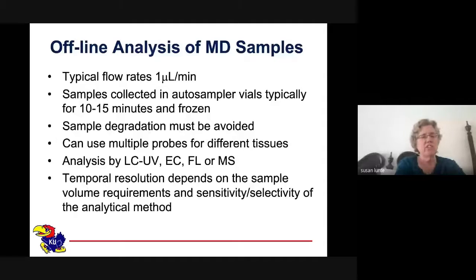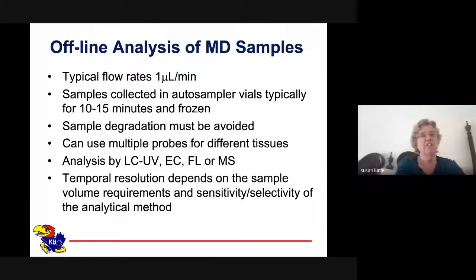the sample won't degrade. With the offline analysis, it's easier to do multiple analyses because you can have multiple fraction collectors for the different probes. And with offline analysis, you can also take a single 15 microliter sample and analyze it by more than one technique. So typically people do LC, UV, EC, fluorescence, or mass spec. But if you use, say, capillary electrophoresis, where you require very little sample to inject, you can actually take that 10 microliter sample and run it on several different types of analysis systems.